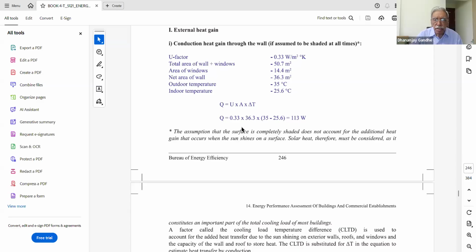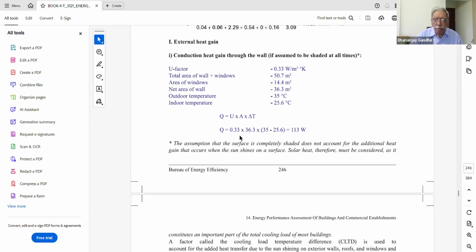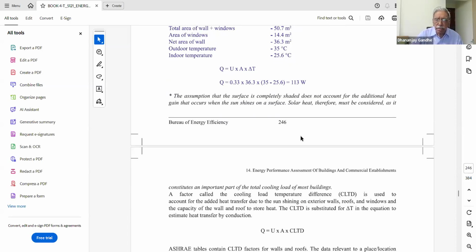So the heat conducted from outside, or heat gain, is worked out as 0.33, which is the U factor, multiplied by the area difference, that means the actual wall area, 50.7 minus 14.4, is equal to 36.3, into the temperature difference. Okay, so this is the heat conduction gain in watts. Okay, it's not calculated in calories or some thermal unit. It's in watts.